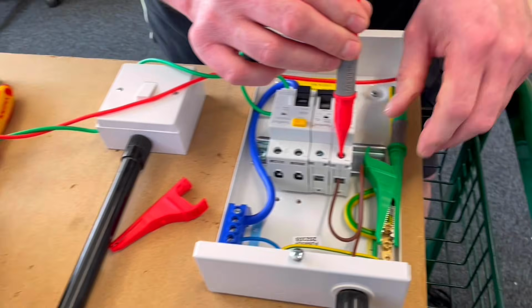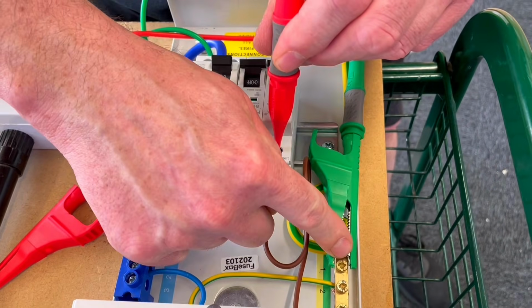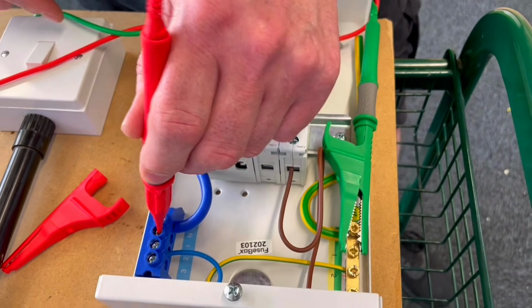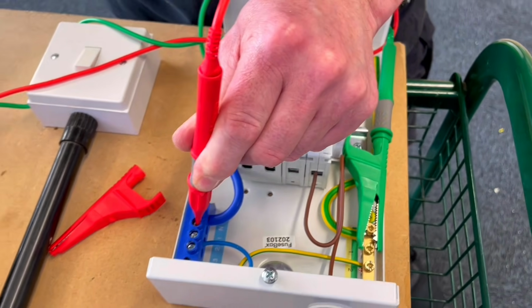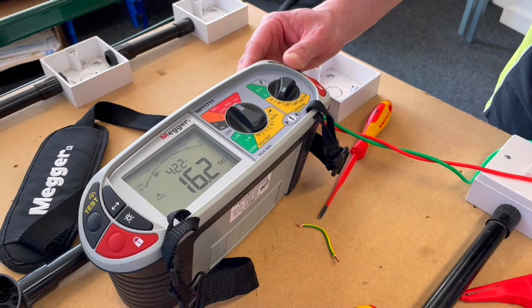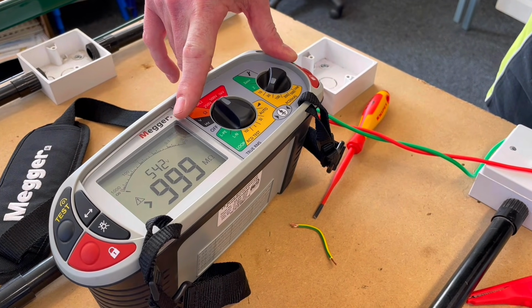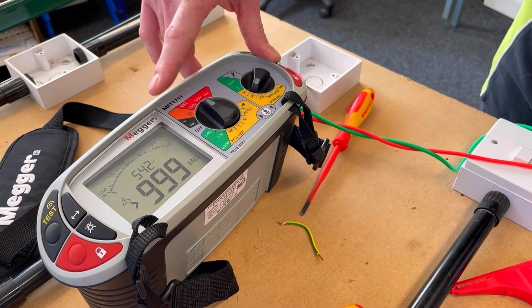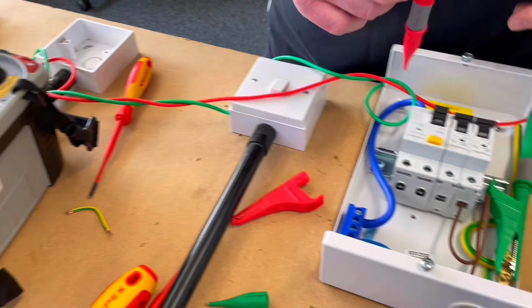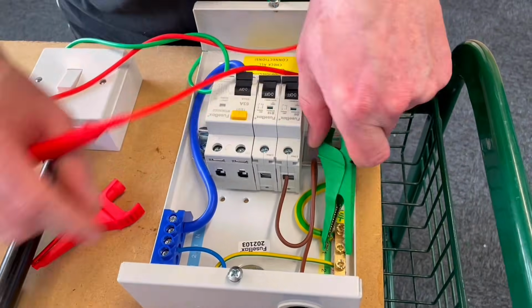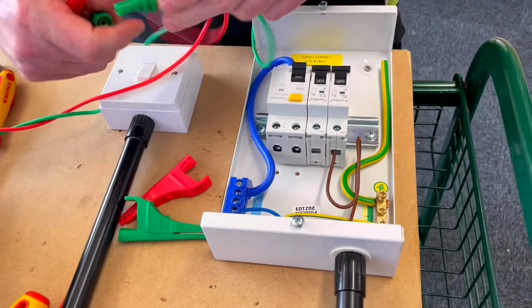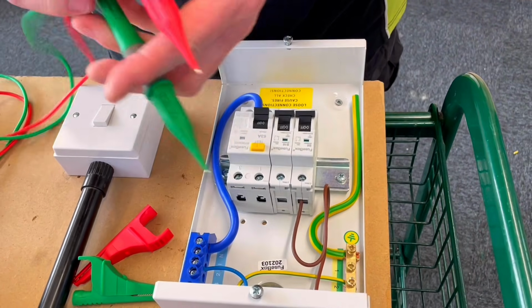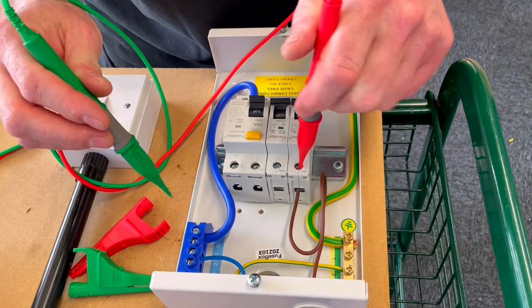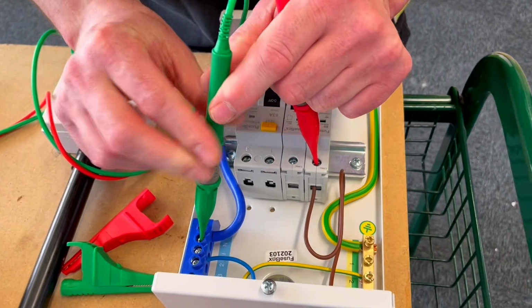We're going to now test between the earth bar and the neutral bar. So if I move my probe across to here, press and hold firmly, and then press the test button once again. And we can see we've got a reading greater than 999 megohms. And then finally, we need to test between the line and the neutral. Again, it doesn't matter which way around your test leads go. So I'm going to test on the line connection and where the neutral is.